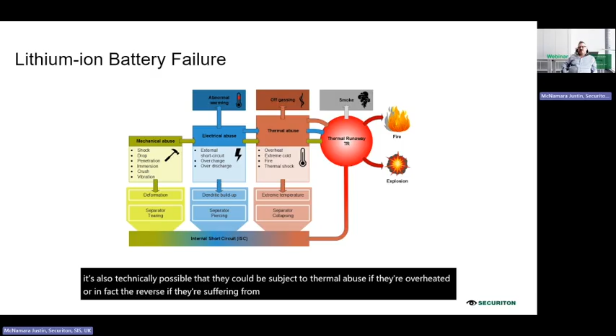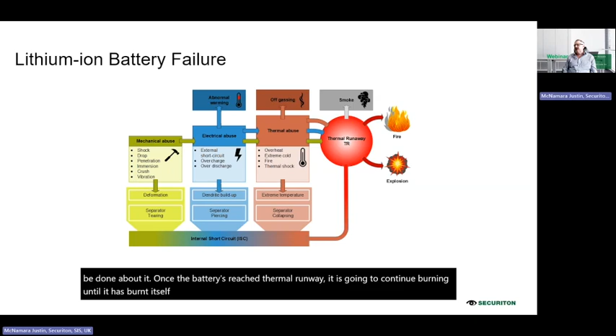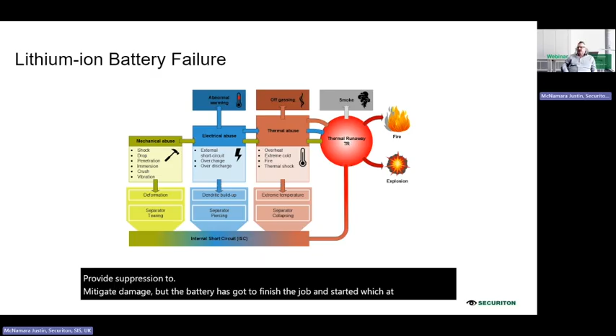When it starts to fail, it will off-gas, giving off volatile organic compounds, or VOCs for short. Left unchecked, the battery will then move into thermal runaway, which produces smoke as part of that process. But at that point it's too late - the battery has gone too far. Chemically, nothing can be done about it. Once it's reached thermal runaway, it will continue burning until it's burnt itself out and finished its job. It's impossible to stop a battery once it's in thermal runaway. Yes, we can provide suppression to mitigate damage, but the battery has got to finish the job it started, which at that point, I'm afraid, is self-destruction.